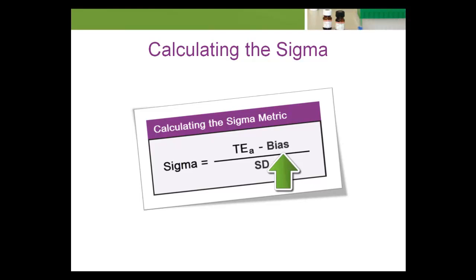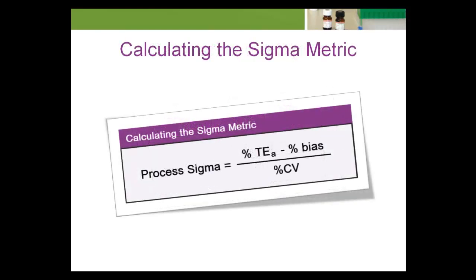Bias is the systematic difference between the expected results obtained by the laboratory's test method and the results that would be obtained from an accepted reference. The reference may be another test method, a standard, or a consensus reference like a proficiency program or an interlaboratory peer comparison program. SD is the total analytical standard deviation of the test method. Equivalently, the quantities can be given as percents: sigma equals percent TEA minus percent bias divided by percent CV, where percent CV is the analytical coefficient of variation of the test method.